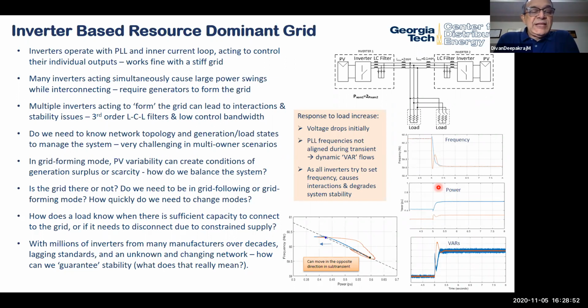What we start seeing is there are a couple of big challenges here. The inverters have to make a lot of decisions: are they in grid-forming mode, or grid-following mode? How do I understand if there's generation surplus or scarcity? How do I balance the system? How does a load know there's sufficient capacity on the system to connect to the grid? And then how do you guarantee stability of the system?